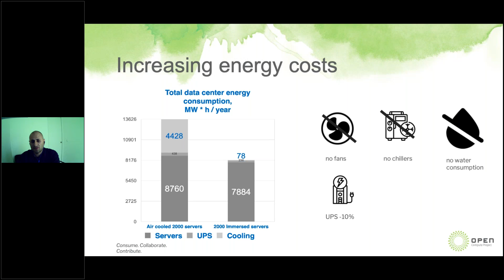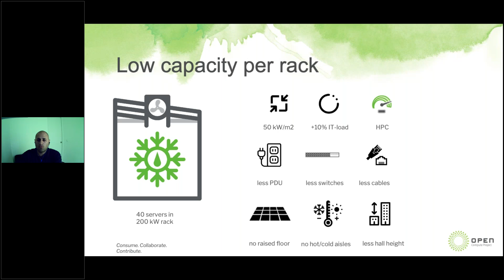With the ratio of IT load to floor space up to 50 kilowatts per square meter, capacity is increased by 10–15% due to the absence of the server fans, high performance servers with an extended quantity of powerful chips, fewer switches per server, fewer PDUs and cables, no raised floor, no hot or cold aisle, and 2 times lower hall height, it means more space for halls.